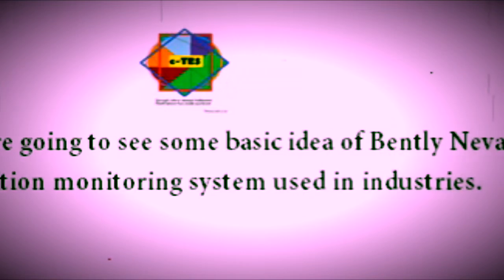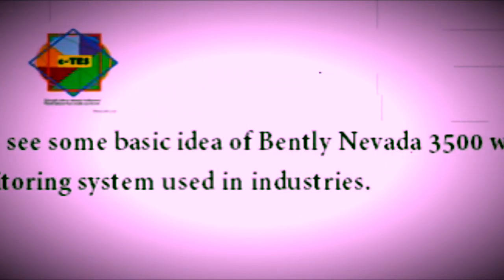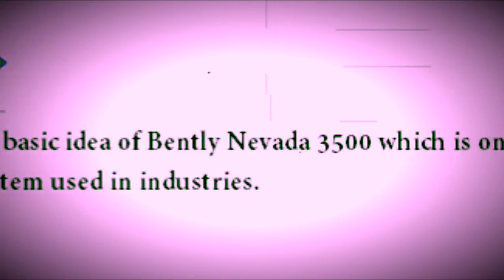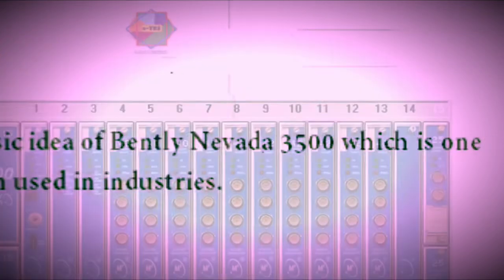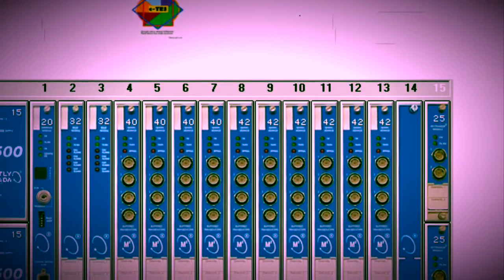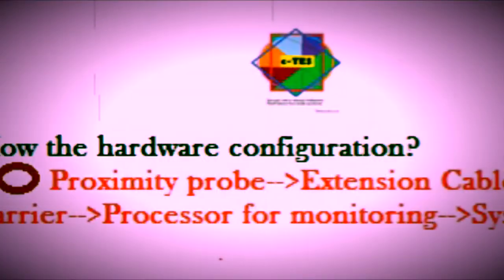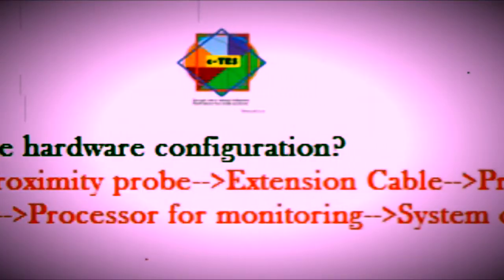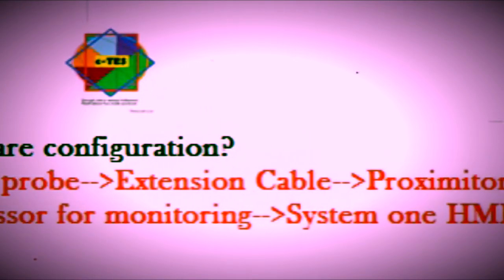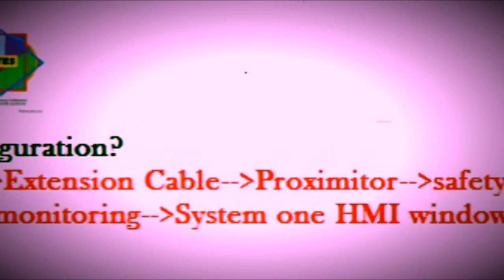The hardware configuration of this system: the probe is connected with an extension cable, then it is connected to the proximitor, then to the safety barrier, then to the processor for monitoring, and then it is connected to the System 1 HMI.